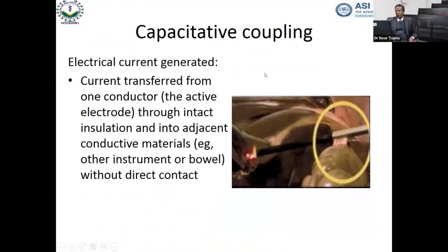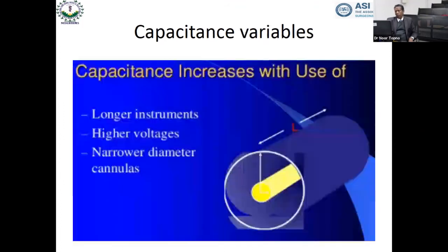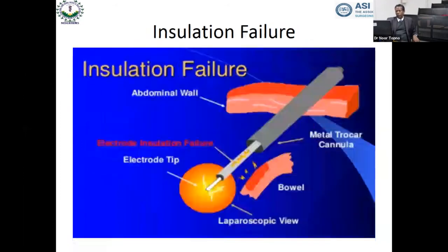Now, this is something interesting which we have been talking about, capacitive coupling. The most important thing here is that for the current transfer to happen, the 2 conductors need not be in touch with each other. Usually, 2 conductors are separated by some sort of insulation. But because of the electromagnetic effect, usually the current jumps across the insulation and goes to the next instrument. And if the instrument is touching some critical thing like a valve, it can cause injury to the bowel. Capacitive coupling depends a lot on the type of instruments you're using, how long the instrument is, and what type of current you're using. If you're using cutting, the chances of damage are less. Coagulation, yes, it is more. And also the diameter of the cannulas when you're doing laparoscopy.